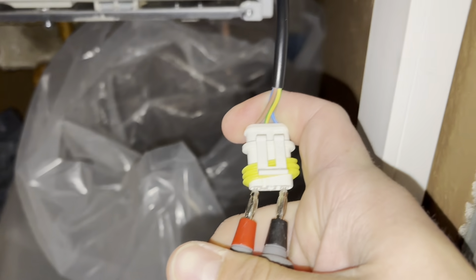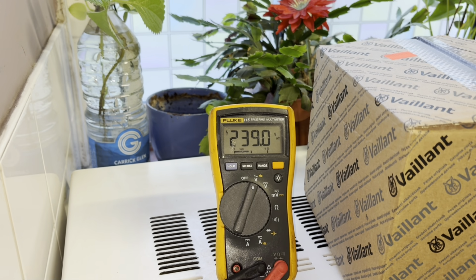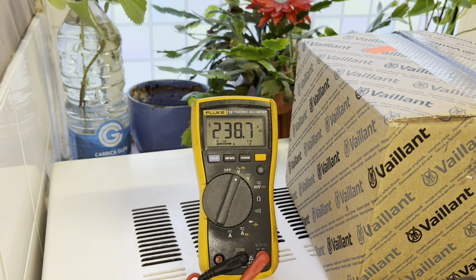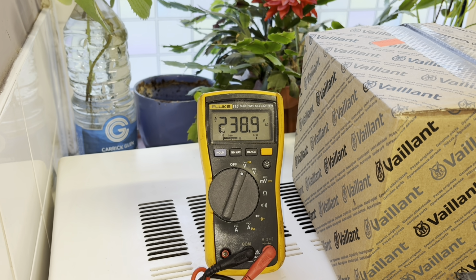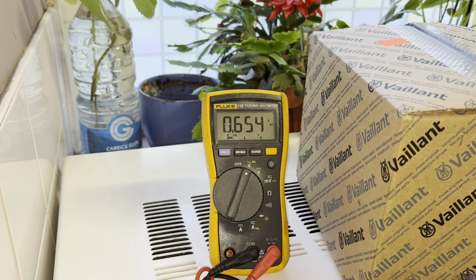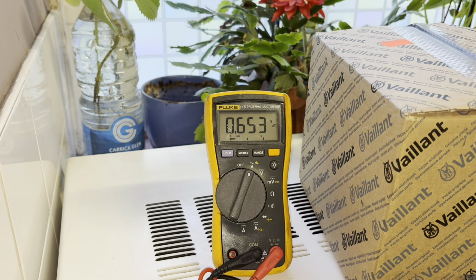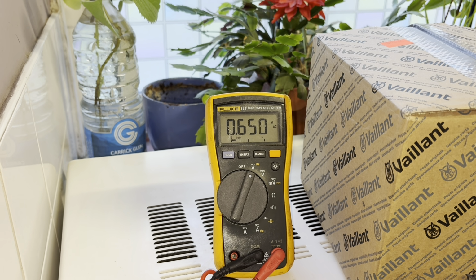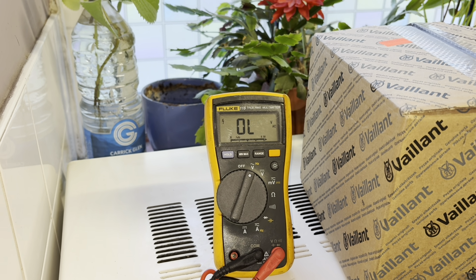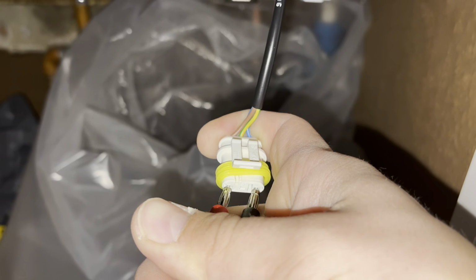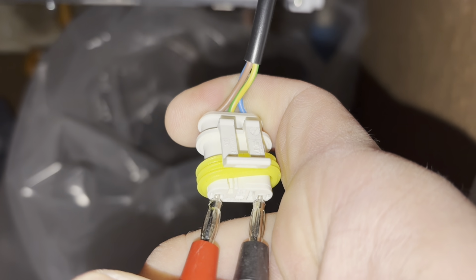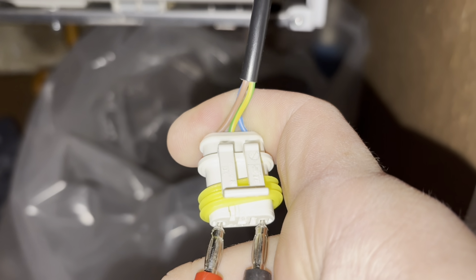Got the two probes in there. Oh, we've got 240. So as the boiler tries to kick in, you get 240 volt, but the pump's not running. So, changing the pump. Make sure you put these in properly as well. Sometimes they don't really touch the little plates inside, so you get a false reading.